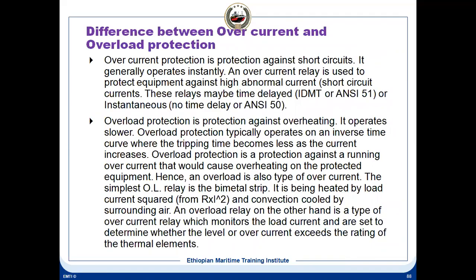Now, the difference between overcurrent and overload protections. Overcurrent protection is protection against short circuits. It generally operates instantaneously. An overcurrent relay is used to protect equipment against a high abnormal current. These relays can be time delayed, or instantaneous type, or inverse time also. Overload protection is against overheating.